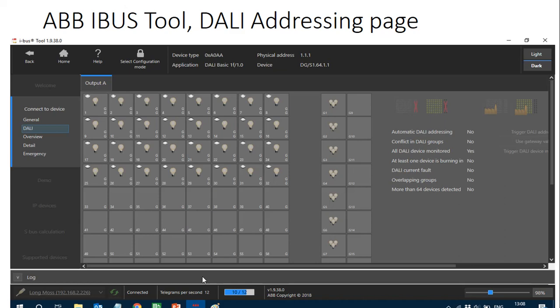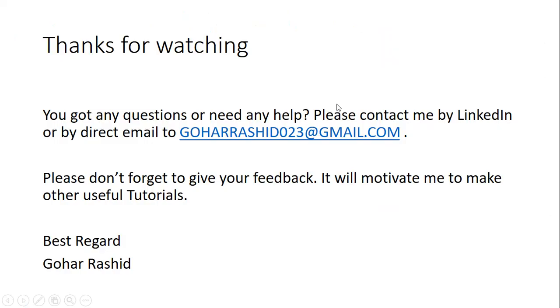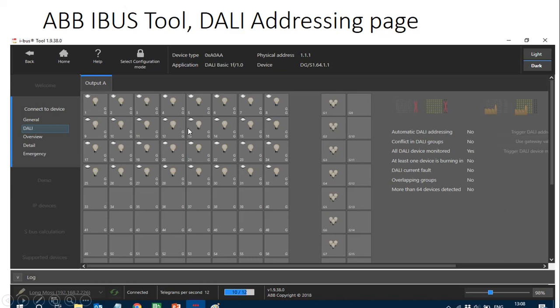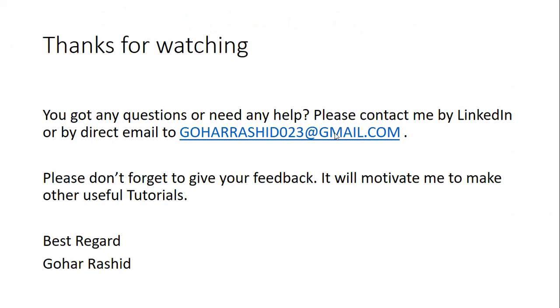Let's go to the next slide. So after you make a connection to USB interface and then you log into DALI device itself, like 1.1.1, then you will be able to see all the lights there and then the groups, you can add them to the groups. So let's suppose we create group one. Group one was chandelier, so I will find out here which one is the chandelier. Let's suppose this is chandelier, so I will link this to, I will drag this to group one, add them to group one. And then group two, let's suppose one to eight was spotlight, so I will add all of them into group two. And after doing this grouping, the KNX lighting will start working as well, so you should be able to control the light after that.